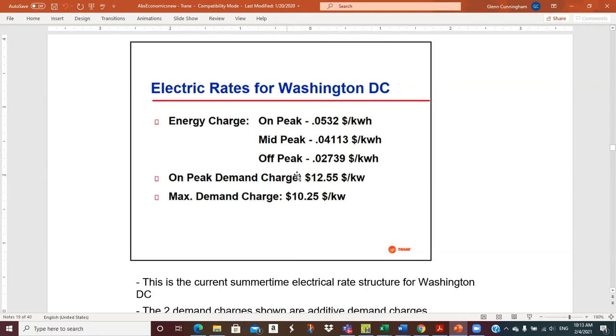But notice the on-peak demand charge is $12.55. The off-peak is probably half of that. And then we have the maximum demand charge of $10.25. So basically, if you set your peak during the on-peak period, each kW is going to cost you $12.55 plus $10.25. And so that's what's really driving this analysis.